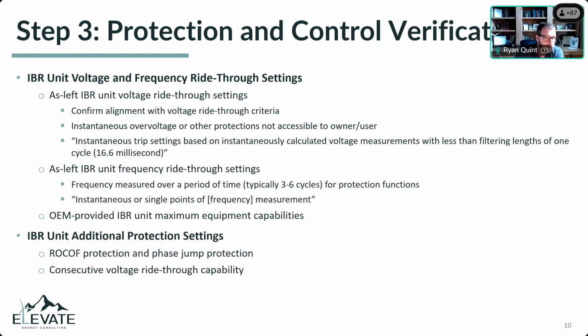Then we move into step 3. We've got the data we need, we've got the OEM information, we've got the site information, then we start evaluating the different pieces of the puzzle, right? So typically we start with the IBR units, we look at the as-left settings, voltage ride-through settings, and make sure that the curves match expectations. Now we're not just doing a curve matching on voltage, but we've found it's very helpful to plot those things, right? Because somebody's always going to ask, well, what's that versus that? So having a visual of the different curves just to understand where they fall is very useful.